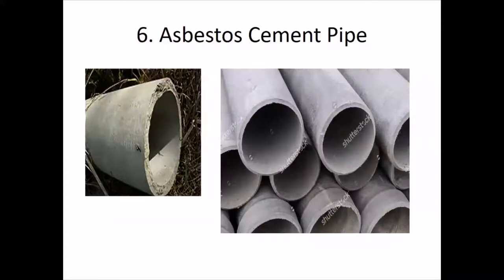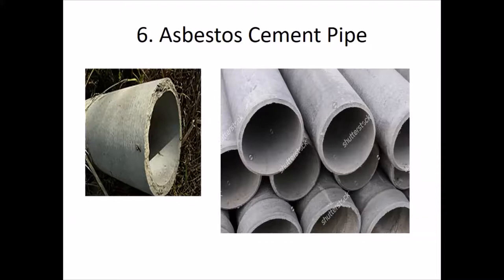Asbestos cement pipes are manufactured from a mixture of cement and asbestos fiber. They are light and can be transported easily, but are very brittle and liable to break if handled carelessly. Cutting, drilling, and jointing can be done easily. These pipes are smooth so carrying capacity is good, and they are not affected by salt, acid, or corrosive agents. They are not intended for high internal pressure and are suitable for distribution systems where internal pressure is low.